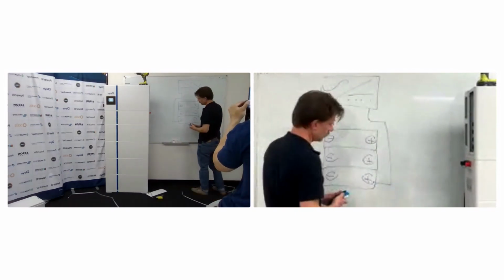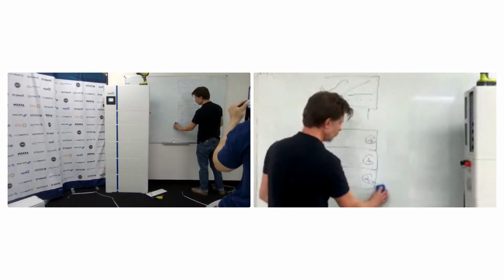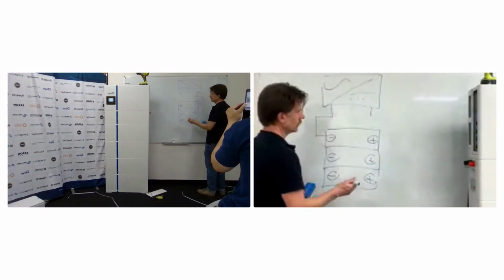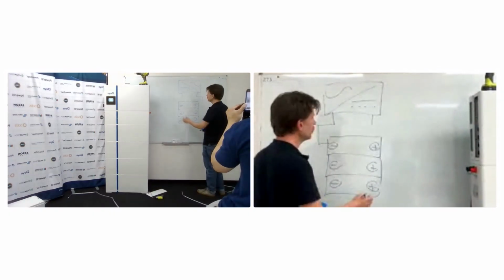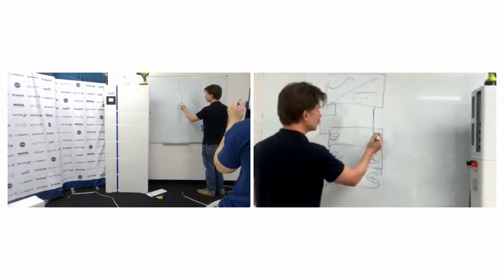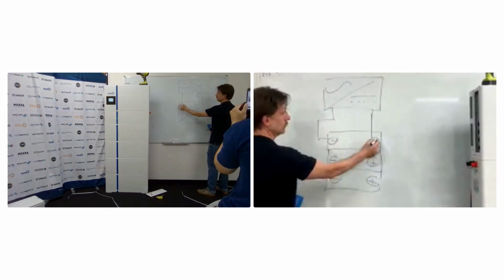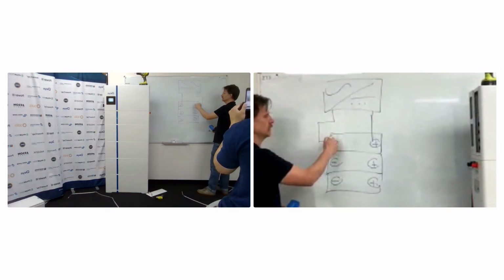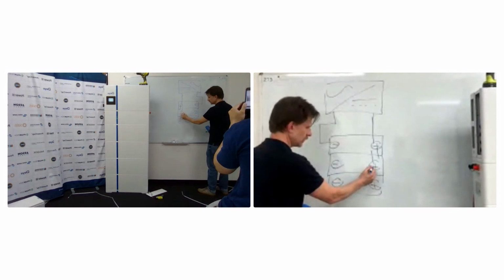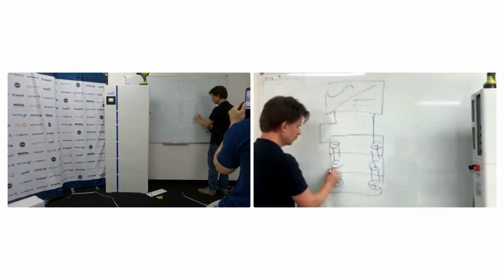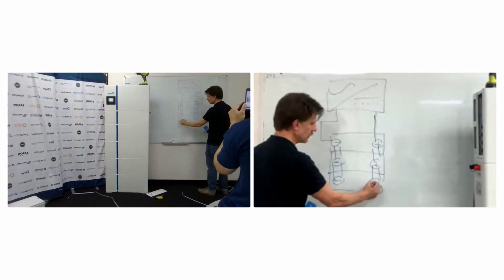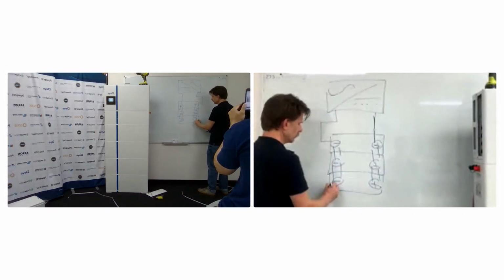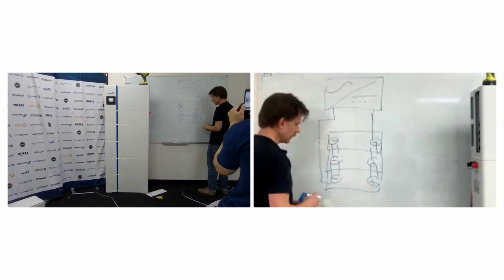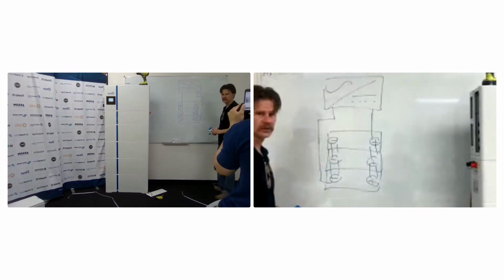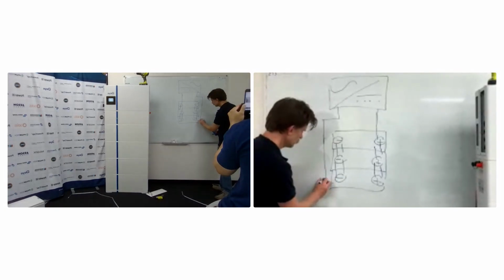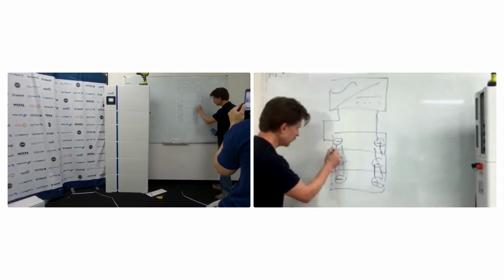In this style of arrangement, the way they've got this wired - and this is what I checked with a multimeter on the BMU when I got it out - is that it's just wired to the top battery, and then it's got 2 connections all the way down. It's not the case that it goes down and then comes back up from the bottom, or something clever like that. I was wondering if the 4 connections were doing that, but it's not. It's just wired in like that, and then it's got a big bus that goes down.